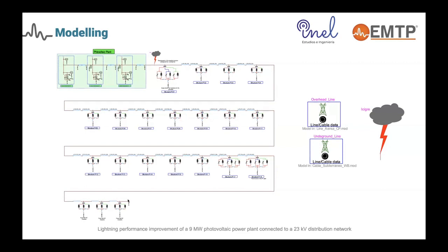Some other elements of the substation have been simplified using grouping models, taking into account different elements like disconnectors, potential transformers, current transformers, bushings, capacitance regarding the bushings of different equipment, the bus bar itself, and so on. This is actually the most critical part after you manage to properly elaborate the line model — being able to represent the substation equipment correctly.